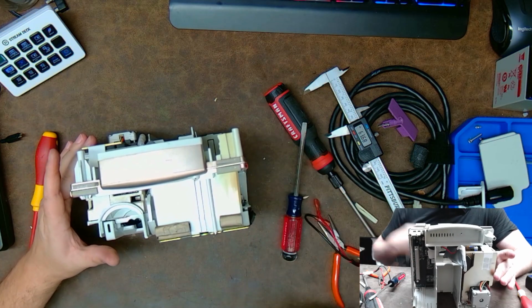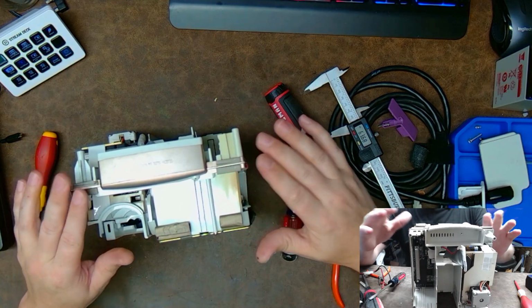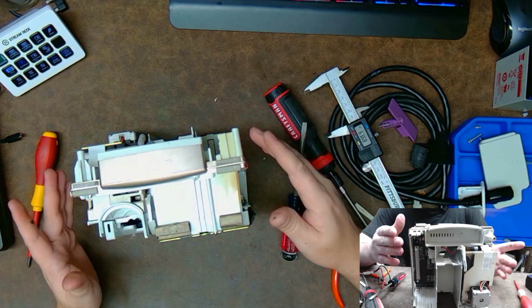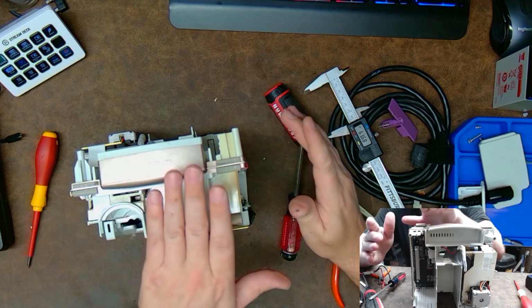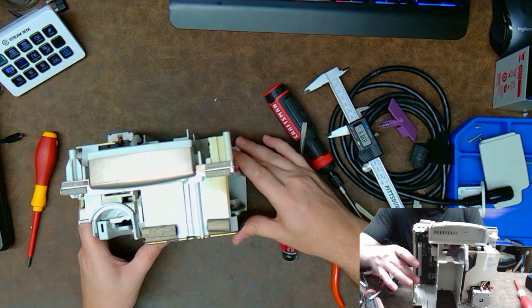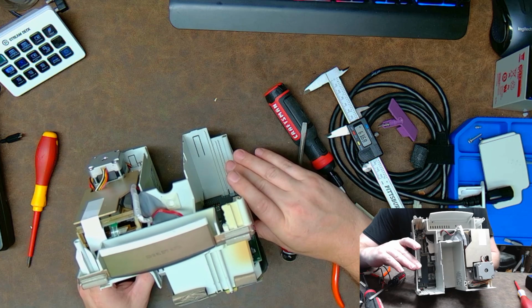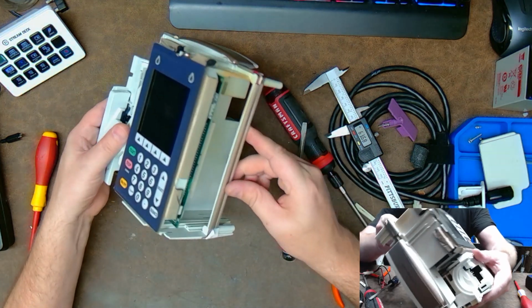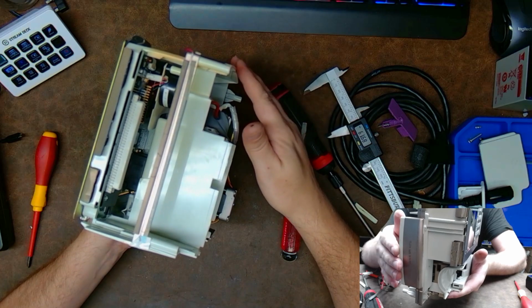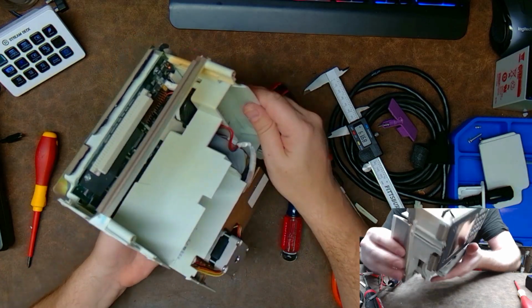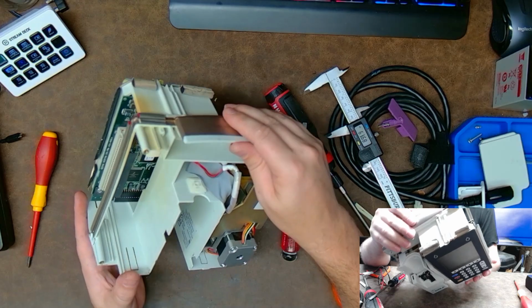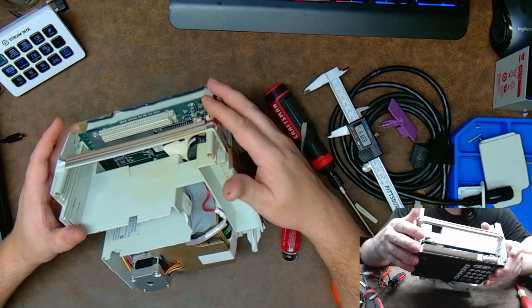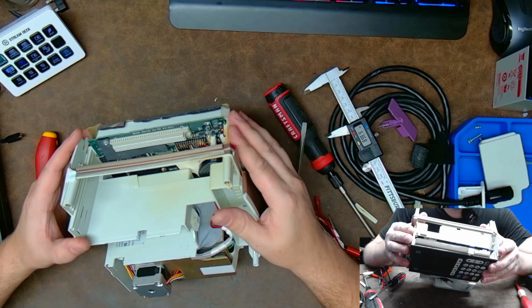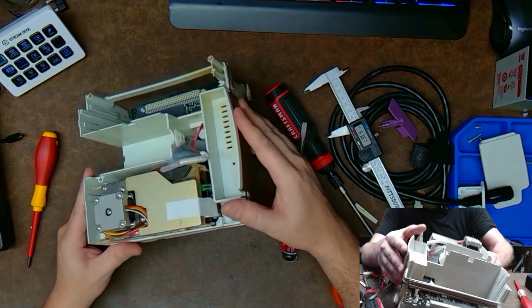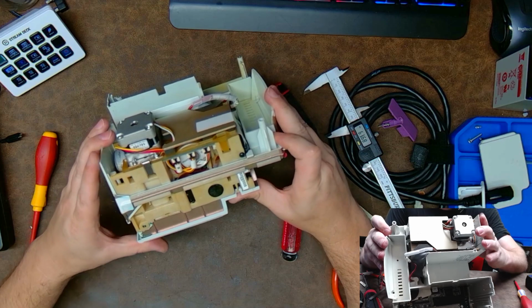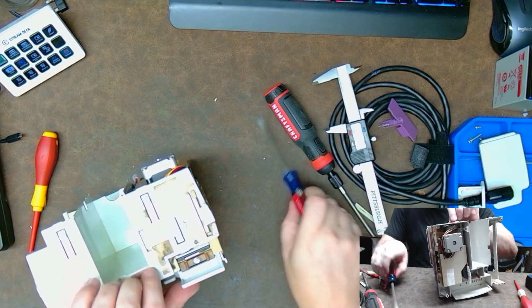Oh, here you go. See, from here you can see it's got grounding pads everywhere to kind of ground out the chassis. I don't know if they have a history of electrical noise on this guy or if it's susceptible to electrical noise, but man, they went off on the grounding on this pump. That's not a bad thing. And I'm trying to find a date code on this guy. Let's see. When was this guy manufactured? I'm not seeing it. We'll probably find it further in on one of the PCBs. It says 2006 Hospira is when that PCB was designed. Yuck. All right, so the pump, I've got a large flathead down here.